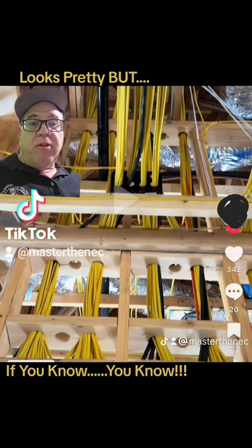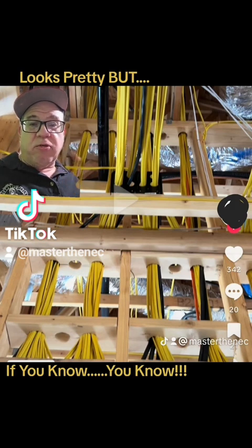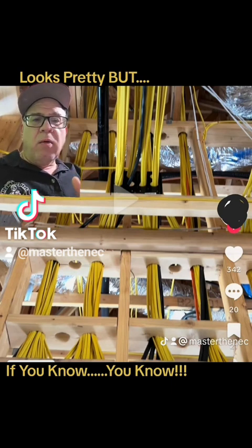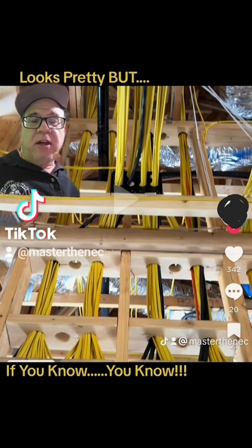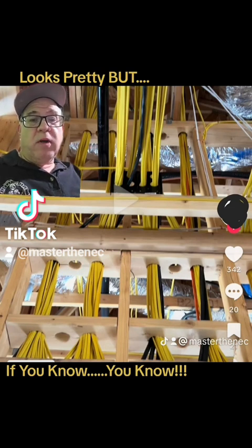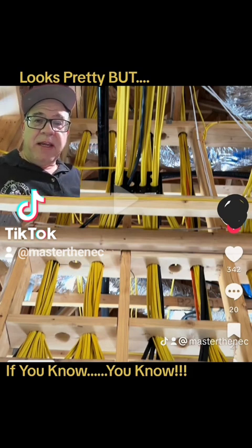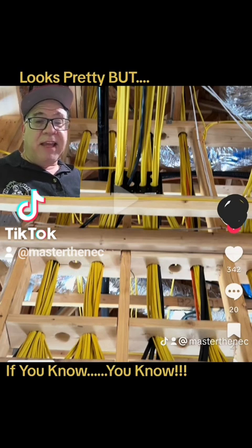In this illustration, I promise you these cables are together more than 24 inches — probably more like four feet. If you look at the top plates and the 2x6s they pass through, 24 inches would only be about four or five of those boards turned on the side. Looking at that run, we have packages of cable assemblies with more than four 12-2s — especially those that look like they have eight 2s in there. Once you start exceeding nine current-carrying conductors in an assembly grouped together, it really starts to affect the ampacity of the conductor.